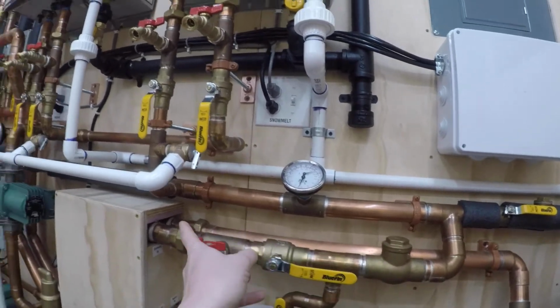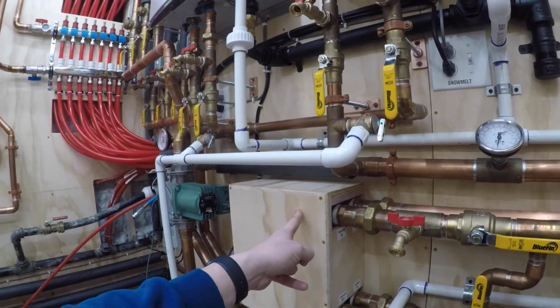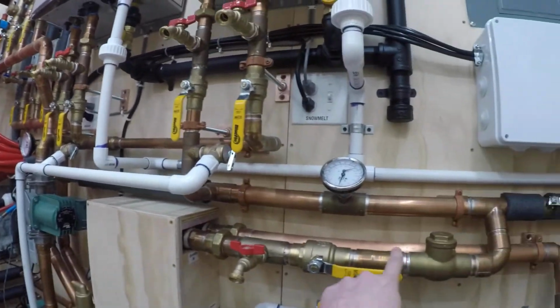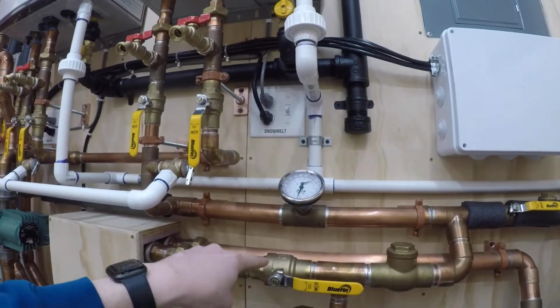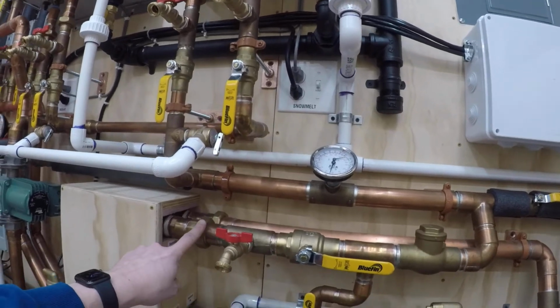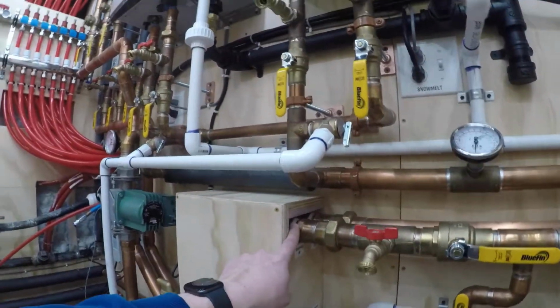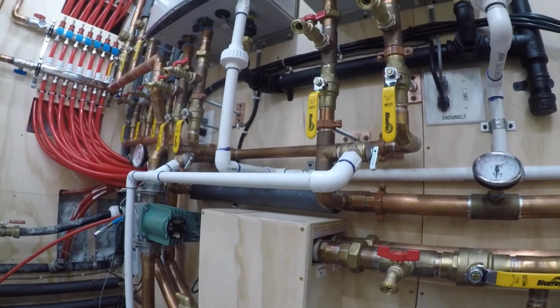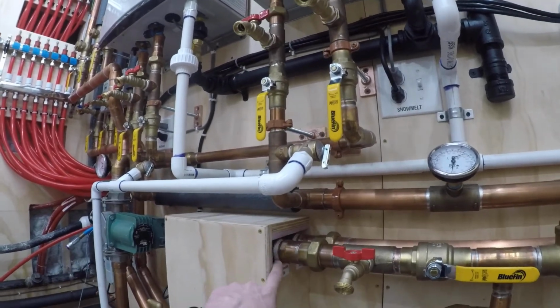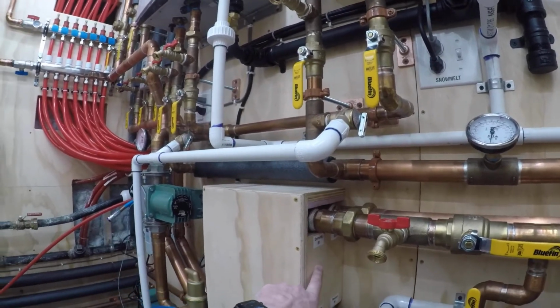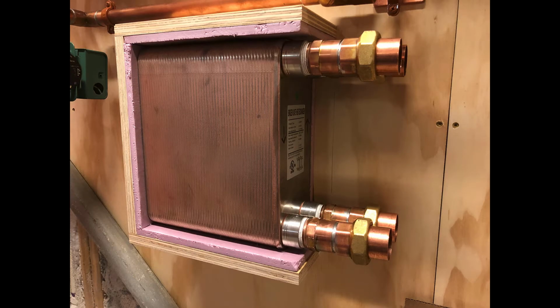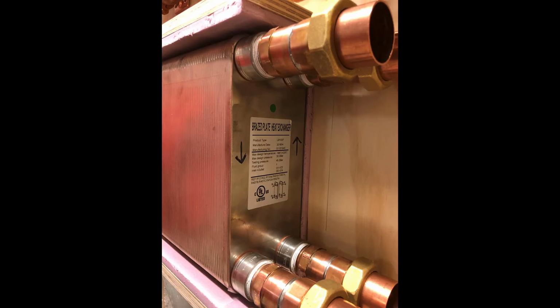It has to go through the flat plate heat exchanger. Okay, so all of my hot water then, domestic hot water, or cold water I should say, unless you're recirculating, comes in through this side of the flat plate. Now this is a 100 plate copper brazed flat plate heat exchanger.